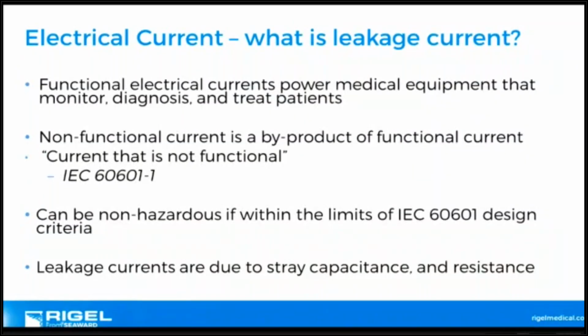What is the analogy? The analogy would be if you've got a hot water system in your household, and you've got your radiators, or you've got your hot water, and you've got a leak somewhere. Well, the only real way to find out where the leak is, because the rest of the functional flow within the system works nicely, is that the pressure tends to drop a bit. So we've got a drip somewhere, we need to see where this leak is. And that's the similar type of thing, that's what earth leakage is.